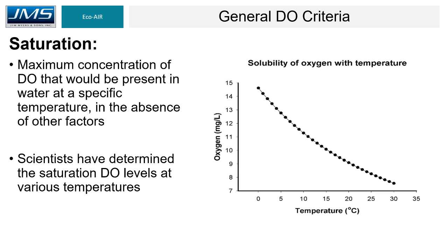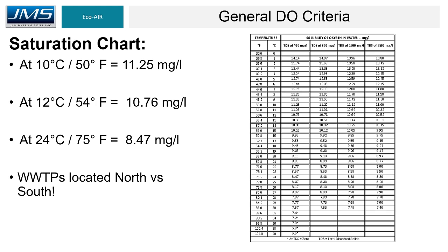Scientists have determined that DO saturation levels vary with temperature, as seen on this slide. At zero degrees Celsius, the saturation point for DO is approximately 15 milligrams per liter. As temperatures decrease, DO saturation increases rather significantly. The saturation chart here shows that at 50 degrees Fahrenheit the solubility of DO is 11.25 milligrams per liter, and at 75 degrees Fahrenheit it is 8.47 milligrams per liter. This means permits in warmer climates physically cannot be as high as those in colder climates because of that saturation limit.